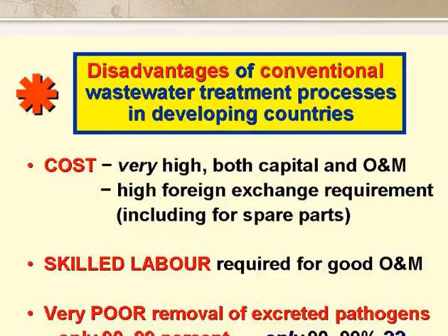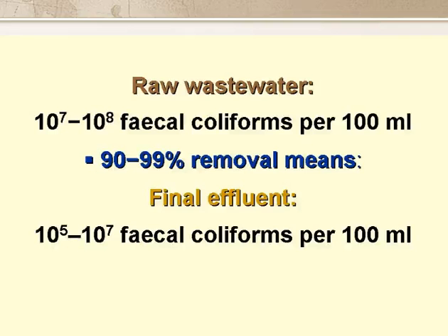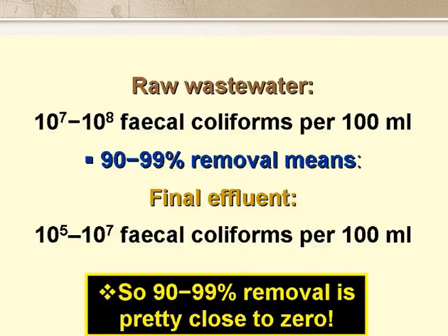In developing countries, conventional wastewater treatment processes such as activated sludge have several major disadvantages. The first is cost — their costs are always very high, with a high requirement for foreign exchange. Secondly, to operate and maintain them properly requires skilled labour that would be better employed in local manufacturing industries. And thirdly, they only achieve a 90 to 99% removal of excreted pathogens. A 90 to 99% removal of BOD would be excellent, but for faecal coliforms it's actually rather poor. Because raw wastewater contains between 10⁷ and 10⁸ faecal coliforms per 100 ml, a removal of 90 to 99% means that the final effluent would contain somewhere between 10⁵ and 10⁷ faecal coliforms per 100 ml — so a 90 to 99% removal of excreted bacteria is pretty close to zero.